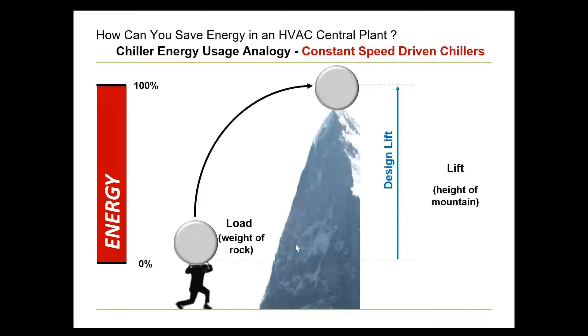So a centrifugal compressor has to be designed for its peak capacity to handle a mass of refrigerant to be elevated from a certain pressure level to a higher pressure level. That is called the design lift. Now, what is that higher pressure level? Lift is nothing else but the difference between the condensing temperature and the evaporating temperature. So a centrifugal chiller should be designed to work at a particular evaporating temperature and condensing temperature. These two temperatures could be different depending on the installation location. In Calcutta, the lift requirement could be different versus the requirement in Delhi or Bangalore. But every centrifugal is subjected to this lift requirement, and it works to generate that particular lift.